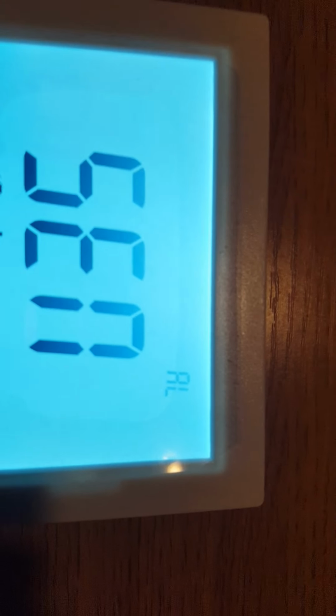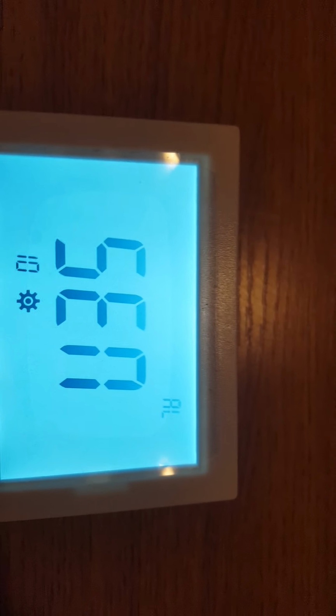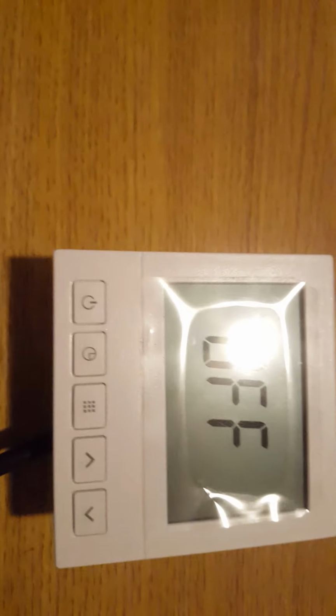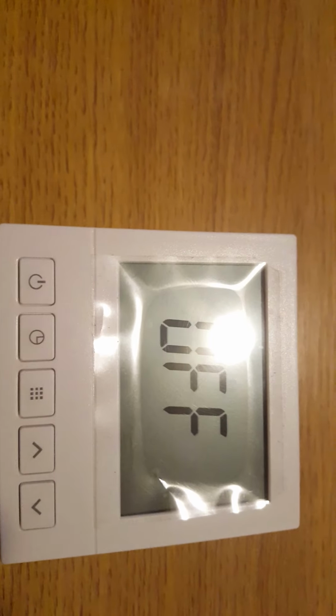Now we go to program number 10. That's the sensor. Now this, sometimes on default, it comes showing all. So it's looking for a floor probe as well, and then it will come up with an error 2, ER2 code. So you need to make sure that program number 10 is on in. That's using the air sensor only, and that's the only parameters that you need to do. Now that's gone off, that's all set. So that's the parameters set.